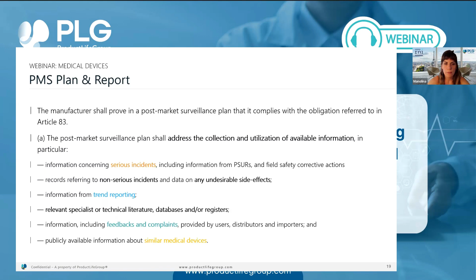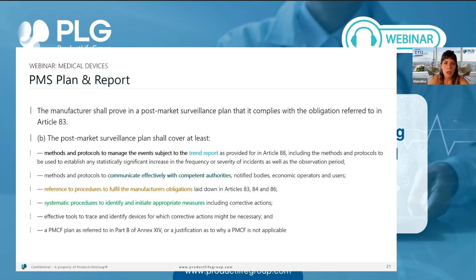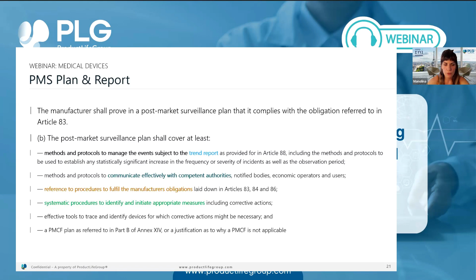And also, the plan should cover at least a proactive and systematic process to collect all the information we talked about previously, and effective and appropriate methods and processes to assess all the collected data. We should establish suitable indicators and threshold values so we can assess the benefit and risk ratio, and also effective and appropriate methods and tools to investigate the complaints and analyze the market-related experience. Also, we should have methods and protocols to manage all the events that are subject to trend reports, to communicate effectively with competent authorities if required, and to reference procedures to fulfill the manufacturer obligations. This is like systematic procedures to identify and initiate appropriate measures.